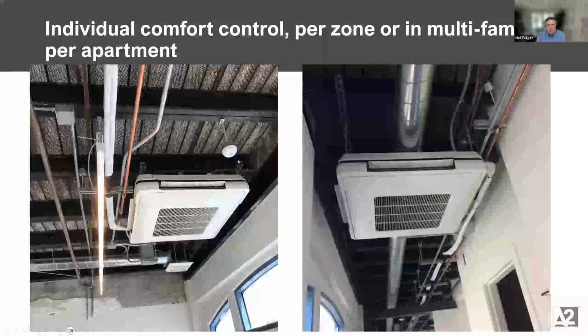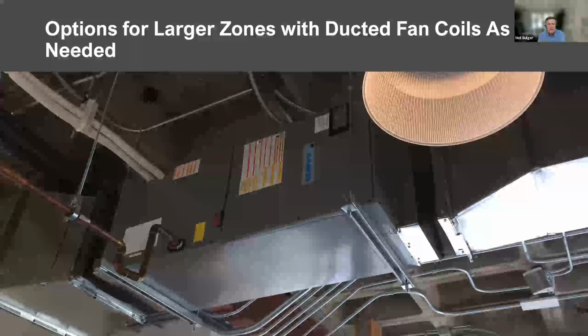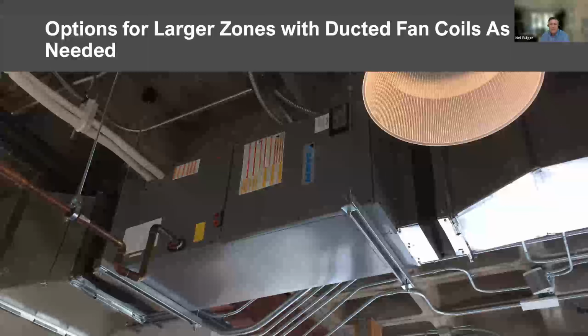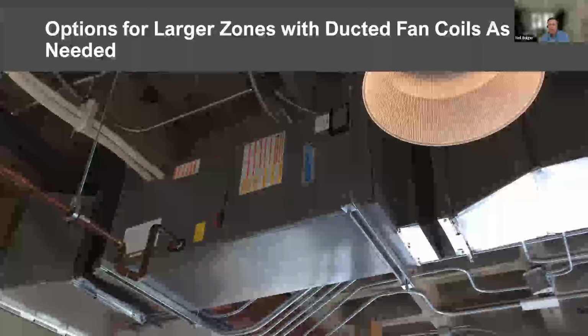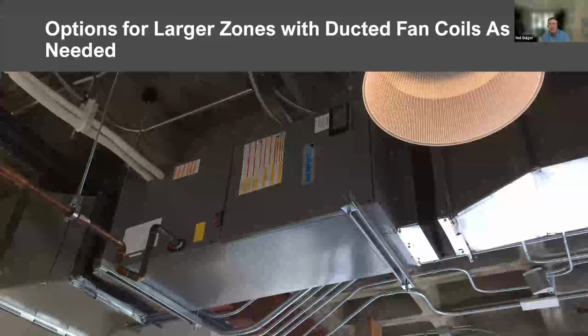Same on the inside, right? You can put these in a lot of spaces. This is an existing retrofit building in Oakland. They were able to line the existing corridors with a bunch of these fan cassettes. You can even see the outside air ducted in this small duct. So they were able to add air conditioning in a building that didn't have air conditioning before. It only had a boiler. They needed to put something in, and this was able to meet their space constraints. A lot of flexibility, and that's often what we see. Big options too, right? Large rooms. This is a ducted fan coil shoved up in the ceiling, serving a large open office space in a three-story office building in Sacramento. Again, it's flexible, and that really drives a lot of value, especially in the architecture realm, when they're trying to work within the constraints of making the building work and the space and a lot of other aspects.